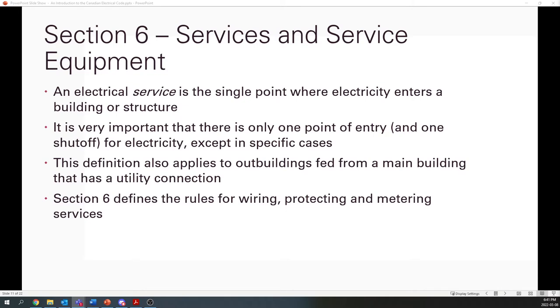It just makes sense to serve it at multiple slightly lower voltages. Still, 25 kV is nothing small. It's definitely medium voltage service, but it just makes more sense to serve it through multiple points. So that is an example where you have one building, though I don't want to call it one building, but I suppose you can get to all the buildings without going outside. The definition of a building gets a little bit gray there, but that's an example of one exception.